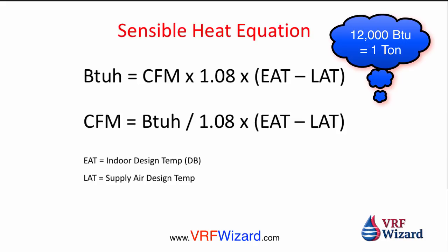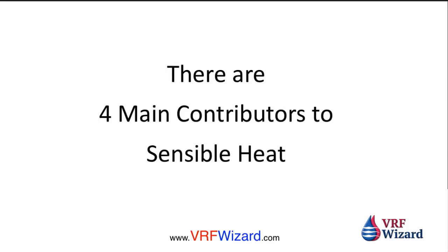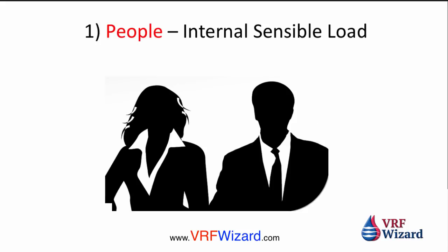Indoor design we're going to use 75°F and leaving air temperature we're going to use 55°F. Sensible heat is a change in temperature — it has nothing to do with moisture; that would be latent heat. We're covering sensible heat and how to figure out CFM for the room. There are four main contributors to sensible heat, the first being people — people give off heat and depending on the activity level, the amount of heat they give off changes.